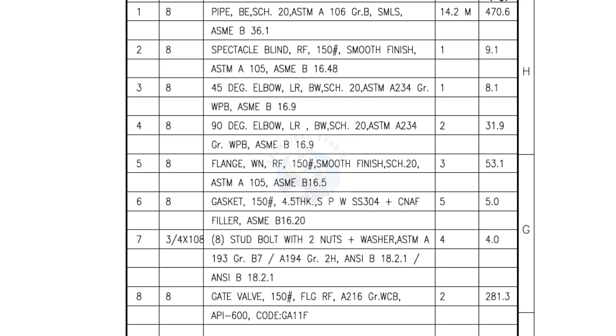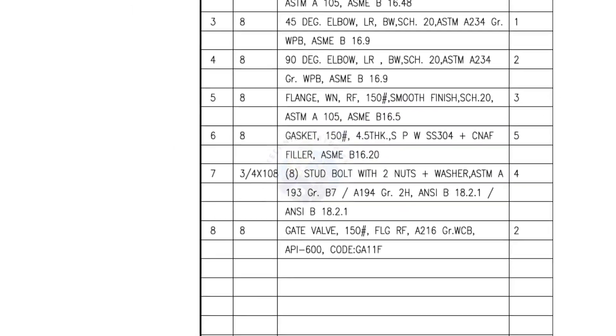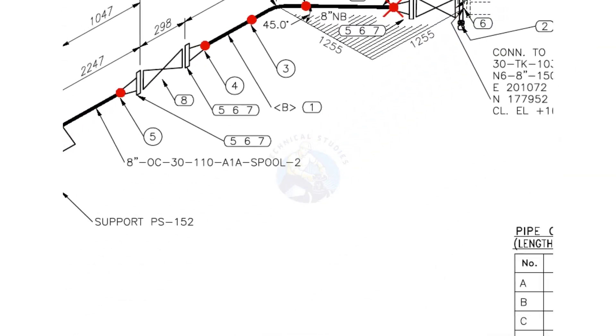How to calculate the takeoff of a long radius 90 degree elbow? The formula is diameter in inches multiplied by 38.1. Let us assume the welding gap is 3 millimeters.